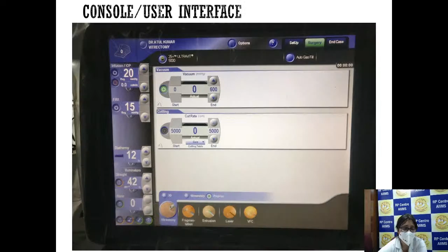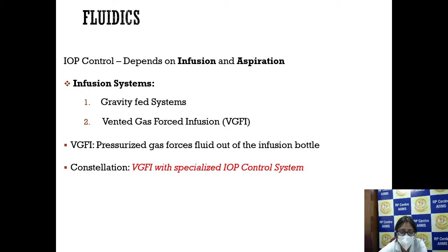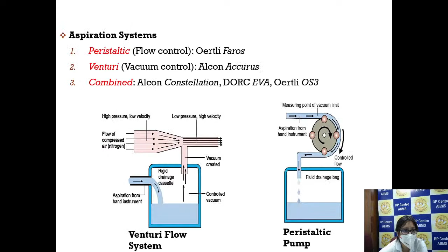Now we come to the fluidics. The IOP control in the eye is controlled by two things: the infusion, which is the inflow, and the aspiration, that is the outflow. Infusion can be two types: the gravity fed and the vented gas forced infusion. In the vented gas forced infusion, pressurized gas forces the fluid out of the infusion bottle. So our Constellation uses VGFI with specialized IOP control systems. The aspiration system is of three types: the peristaltic, venturi, and combined.